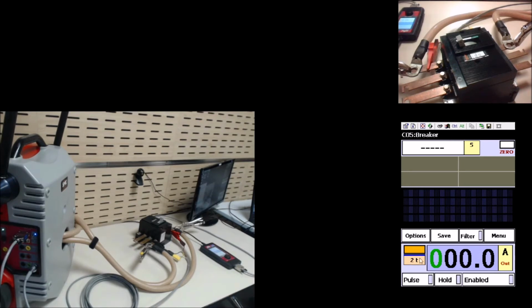reminding me that I am starting a test session, so I might need to have the Raptor calibrate the connected load. Okay, this is important, especially for the tests that take a very short duration. It is important that the Raptor pre-calibrates the load in order to inject the selected amount of current from the very beginning. Okay, so I am just entering a small amount of current, for example 100 ampere, enable the output and activate just for a short while. Okay, now you see it's disappeared, the orange indicator here.